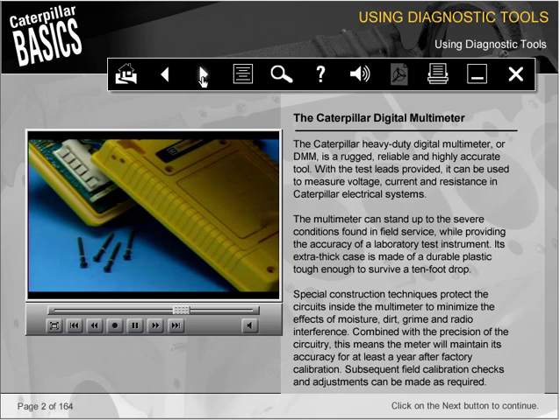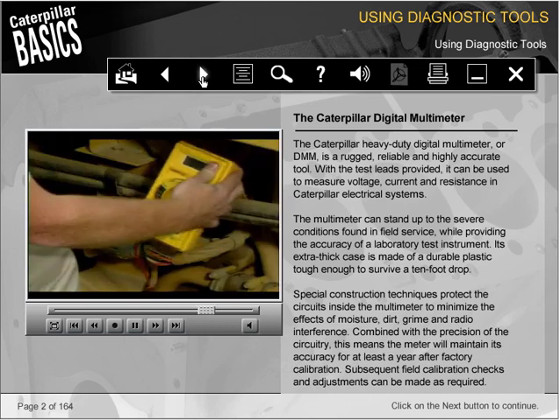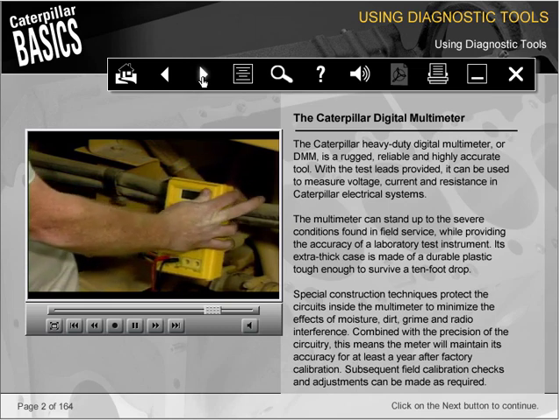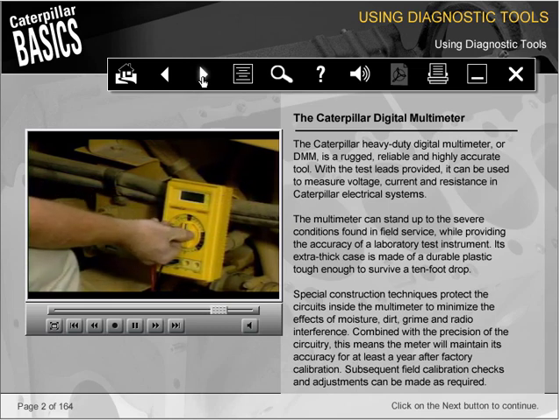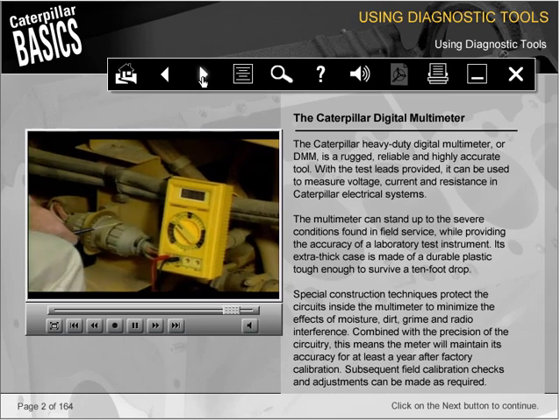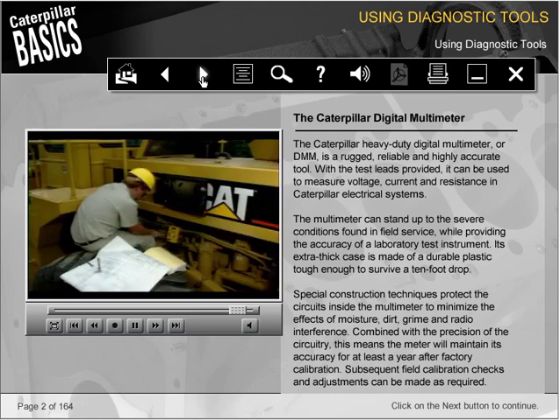Special construction techniques protect the circuits inside the multimeter to minimize the effects of moisture, dirt, grime, and radio interference. Combined with the precision of the circuitry, this means the meter will maintain its accuracy for at least a year after factory calibration. Subsequent field calibration checks and adjustments can be made as required.